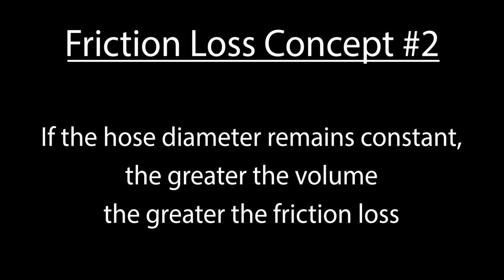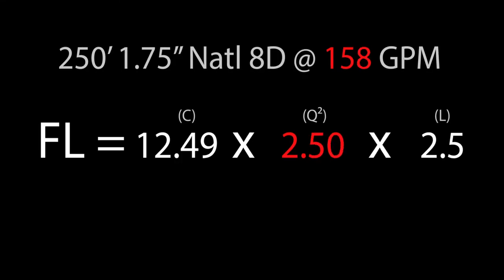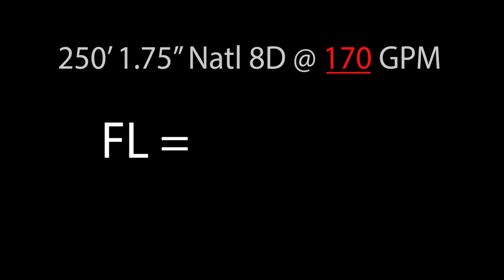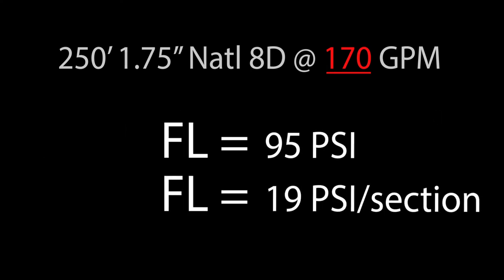The second friction loss concept states that if the hose diameter stays constant, increasing volume increases friction loss. If we increase our volume to 170 GPM, our total friction loss will increase to 95 PSI, or 19 PSI per section.